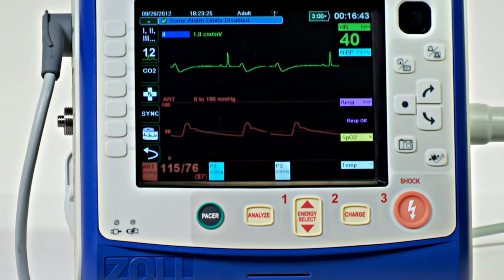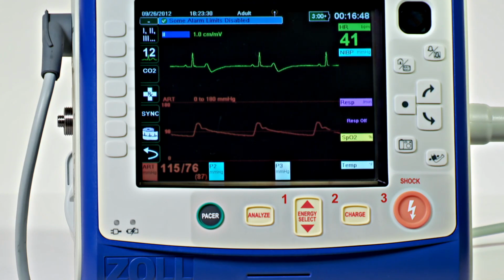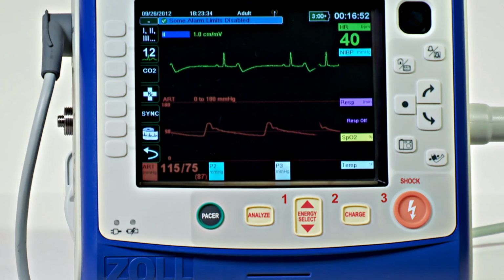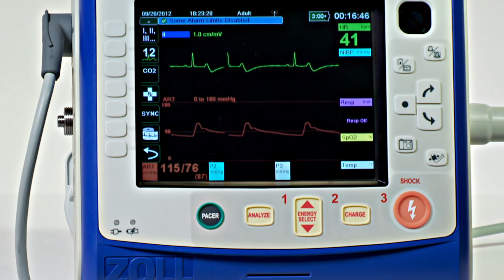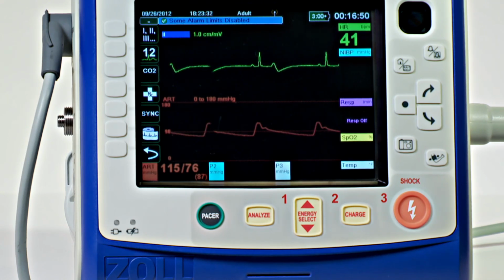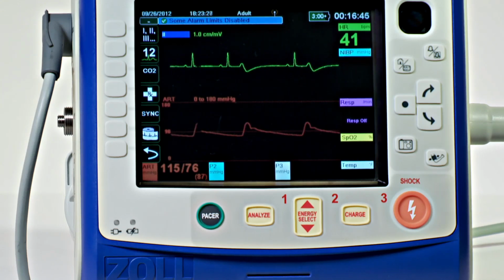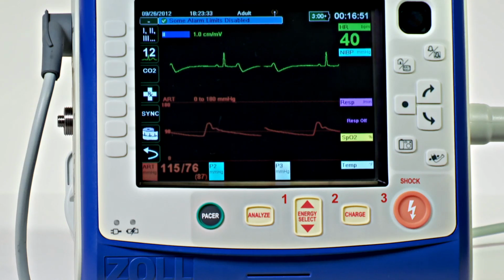After attaching and zeroing a transducer, the device displays the invasive pressure systolic, diastolic, and mean values in the IBP channel's numeric display and optionally, if enabled through the unit's waveform select menu, the waveform for that IBP channel. This device will allow you to specify a label that identifies the channel's IBP measurement and to select a display format for the numeric display. The unit displays the waveform scales after you zero the transducer. When the unit accepts the 0 reference value, it determines the waveform scales and displays them.